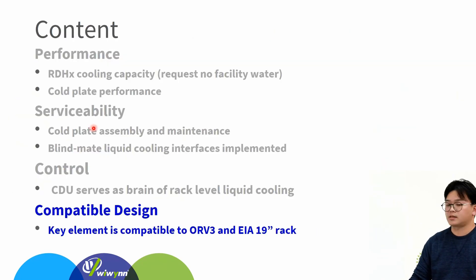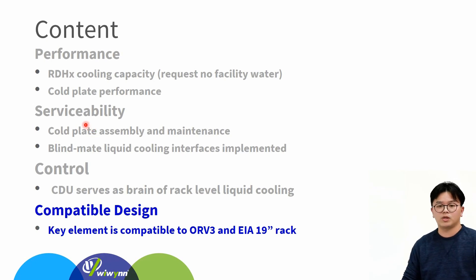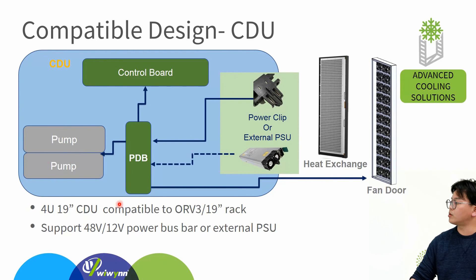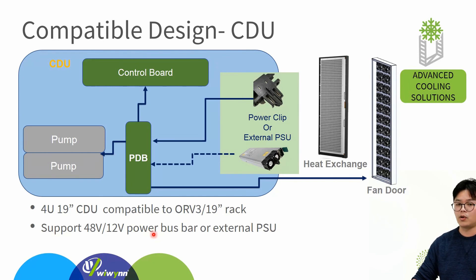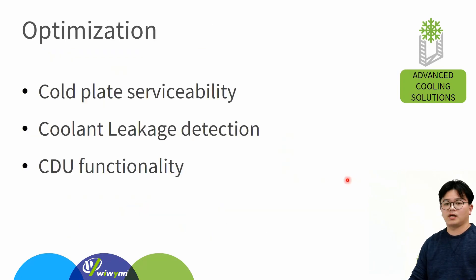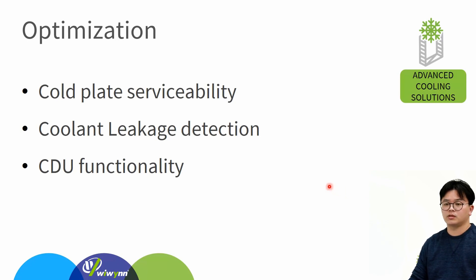The last design factor is compatible design. The CDU design will be implemented not only in Open Rack but also in 19-inch rack. For CDU dimensions, we will design a 4U 19-inch CDU with an extra kit to fit Open Rack. For power, we will support 48V and 12V with a power bus bar, and design the possibility to use an external PSU to support 19-inch rack. We will optimize the cold plate design for better serviceability. Regarding coolant leakage — a main concern in liquid cooling — we will optimize the design for leakage safety.